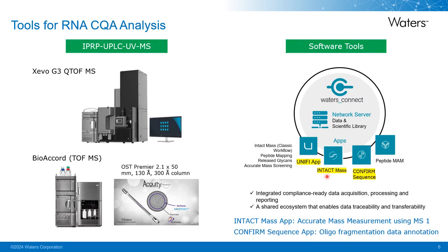The Intact Mass app is general-purpose software that can measure accurate mass for a variety of sample types, including mRNA or synthetic oligos. It takes MS channel 1 data, performs charge deconvolution, and assigns accurate mass information. The CONFIRM Sequence app is a more specific tool that can annotate MS-MS fragmentation data from oligos, matching experimental data with in silico-generated fragment ions. Scientists can review the output of the matched spectrum to assess how accurately and confidently the assignment was made.